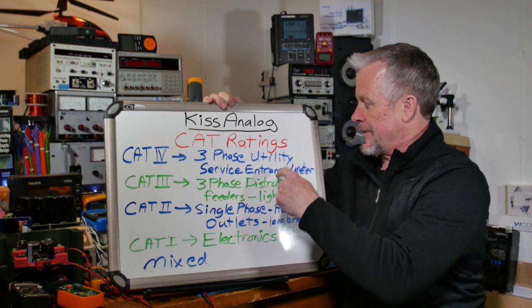But let's talk about those safety features. Okay, guys, some of these features you might find in a digital multimeter. Number one is a fuse, that high rupture capacity HRC fuse, the ceramic one. If it is a true HRC type fuse, it will have a UL listing on it. If you see ceramic ones without all the writing on them, without the UL mark or some other safety agency mark, it's not a true high rupture capacity fuse. It could be, it's just not certified, but a ceramic structure is pretty strong, okay?